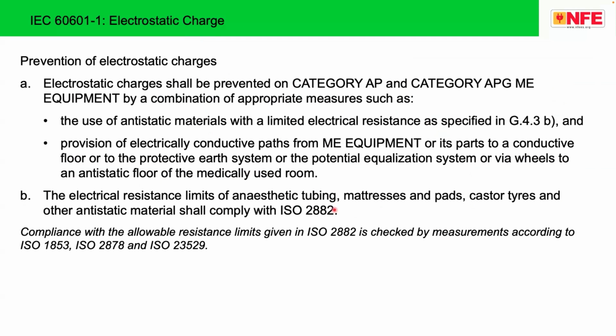Electrostatic charge control in the biomedical equipment is the responsibility of the equipment manufacturer. And if the equipment is tested as per the standards, then of course it is already taken care of by the equipment. The electrostatic charges in locations categorized as AP or APG, that means areas where a large amount of explosive gases are present, are also already taken care of by the equipment manufacturer.